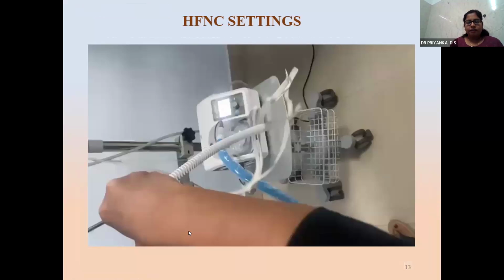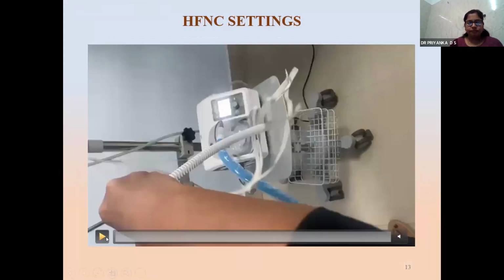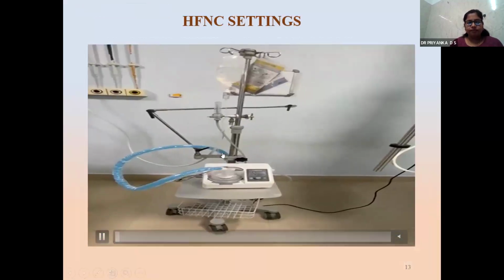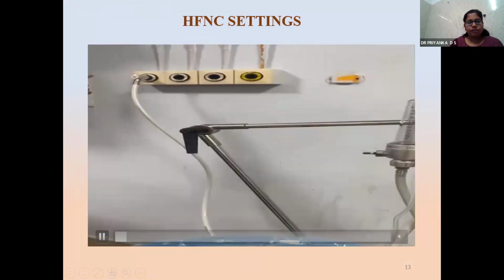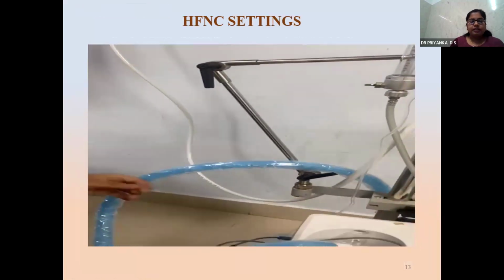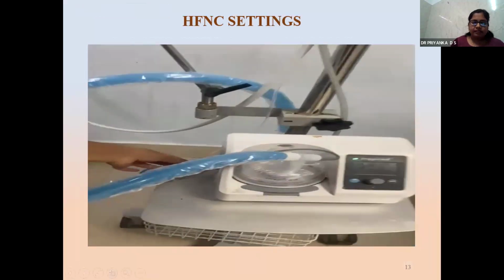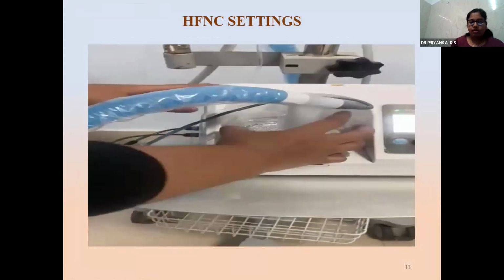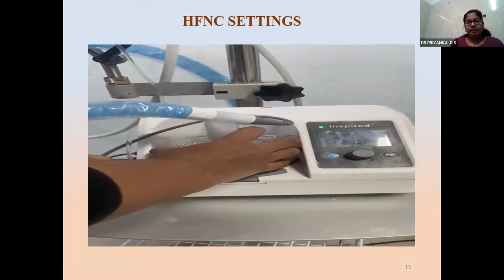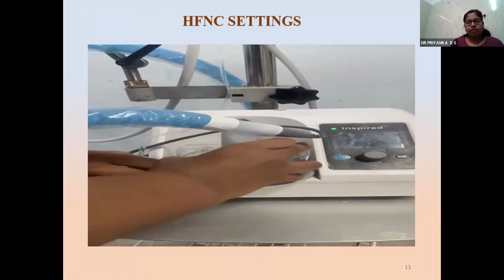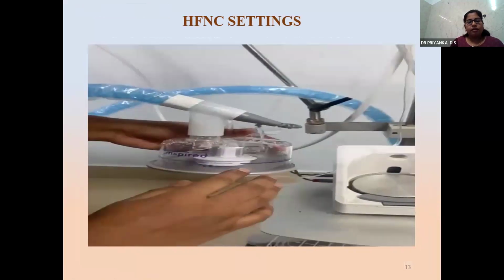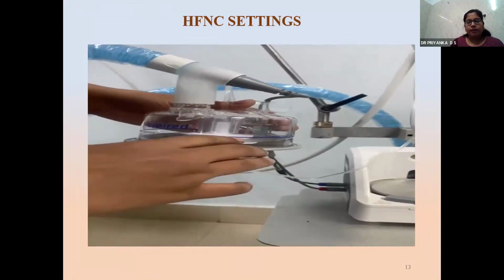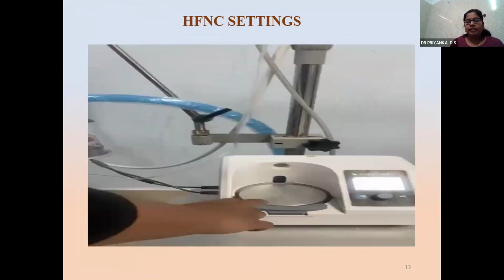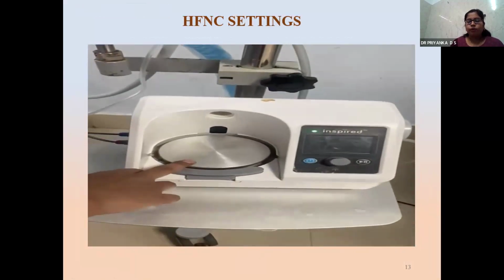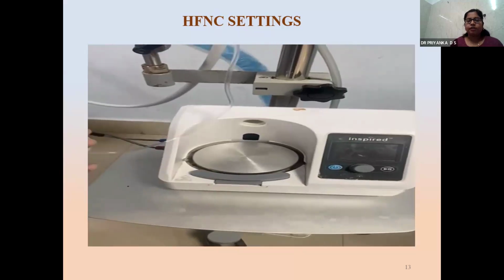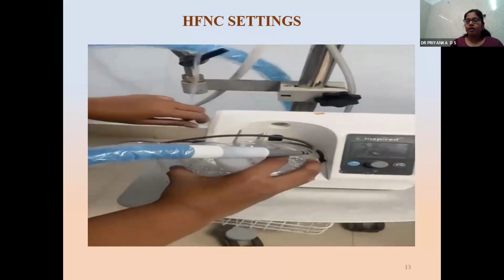Now we'll see the live demonstration of the HFNO settings. This is the HFNO machine with central oxygen supply. This is the flow sensor. This is the humidifier, with the distilled water always filled up to the mark shown here. Underneath the humidifier is the aluminum plate which gets warmed up, and the temperature will be transmitted to the air gas mixture in the air blender.